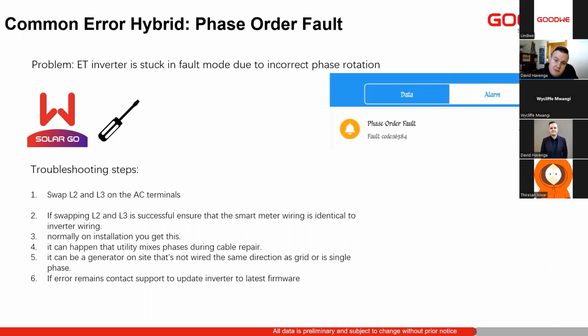So very often we can swap two of the lives, 2 and 3, on the AC terminals, and then switch the grid back onto the inverter. If the error is cleared, then we know, wonderful, we've solved the issue, and we can continue. But it's very important when we do this, if we swap the lives on the inverter and we're using zero export or the unbalanced output function, it means we need to swap it by the smart meter as well. So unless we've swapped the phases by the utility coming in, if we just swapped it by the inverter breaker or under the inverter, we need to go and swap it by the smart meter as well and move the CTs around to the correct phases. So that's very important.